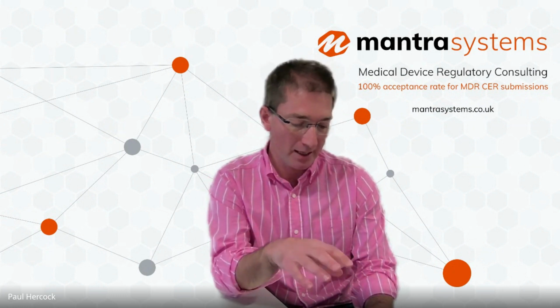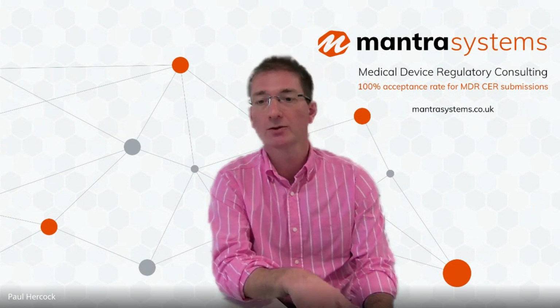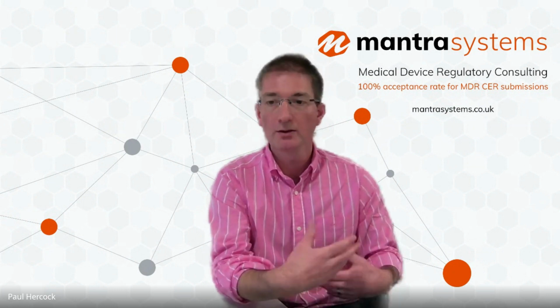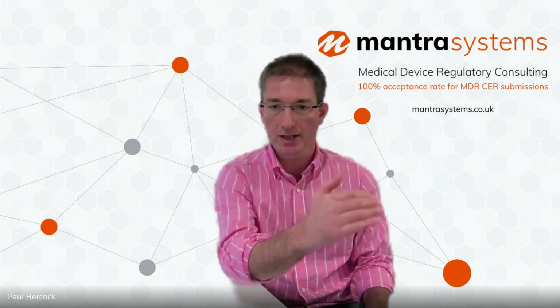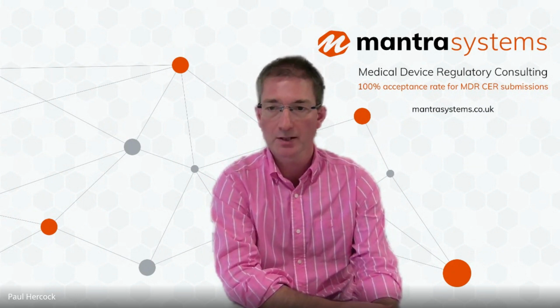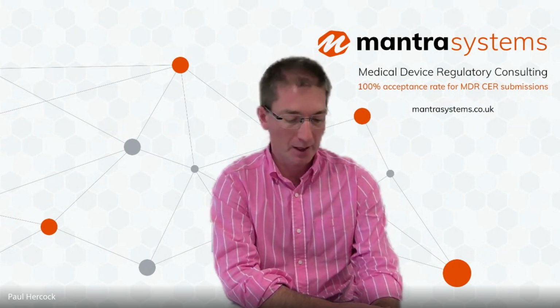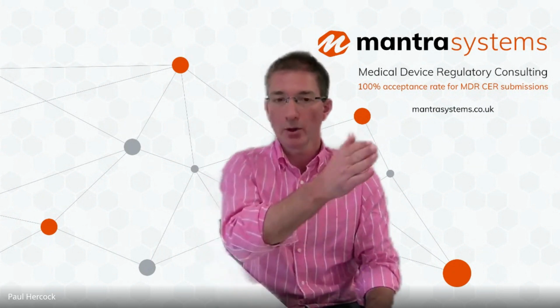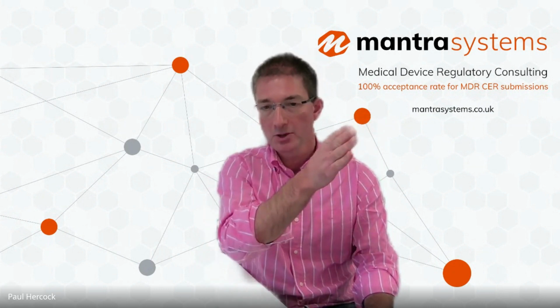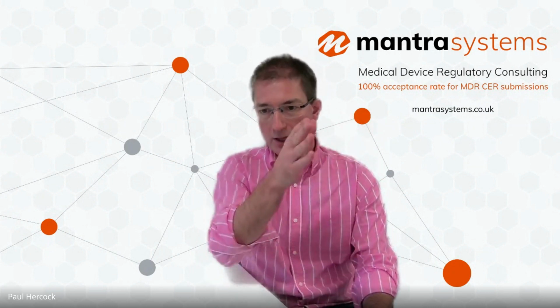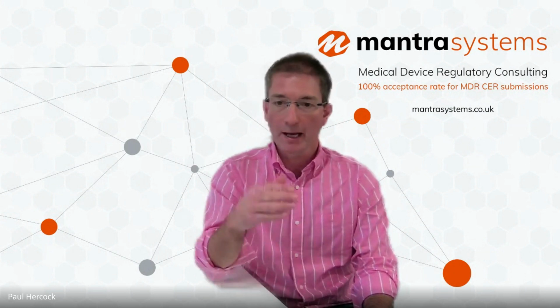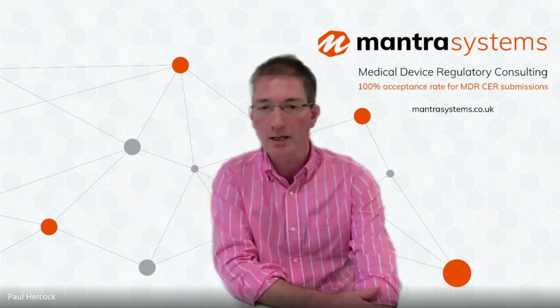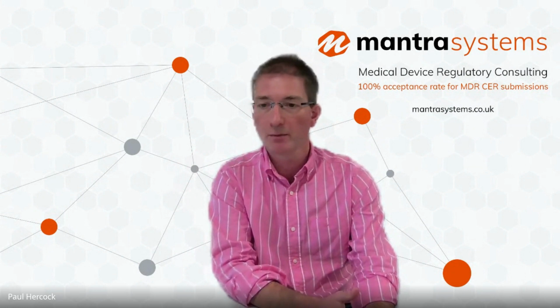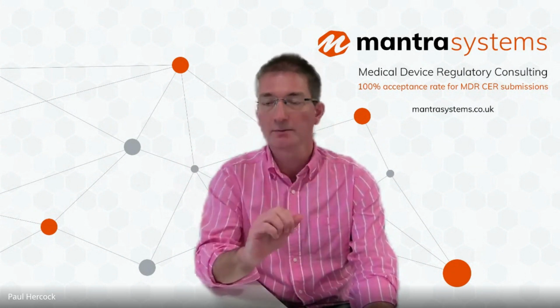physical contact with the patient. But for hardware devices, all three sets of characteristics will be significant. So you need to list them. And really what you're doing is making a comparison between the subject device and the equivalent device, and then making a comment on the likely impact of any differences on safety and performance for each line item.